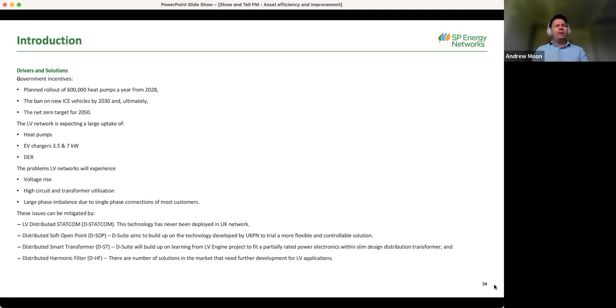The top one here has never been done at UK level, which is an LV StatCom. LV StatComs are mainly used to control power factor and reactive power. They can do that very fast and provide rapid response. They can also improve phase imbalance. They're connected to three phases and can share power between the phases, and if they're placed optimally, they can improve the phase imbalance issue where they're placed. So these are very promising technologies, and we'll roll into what we've done for work package 1. Next slide, please.